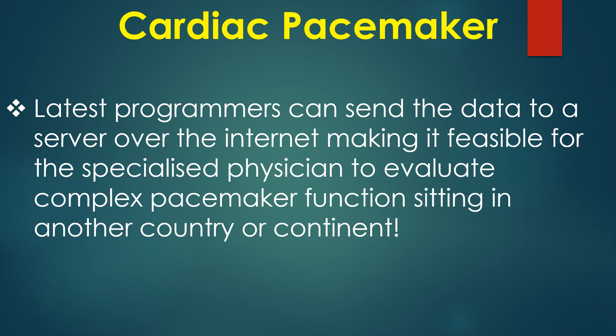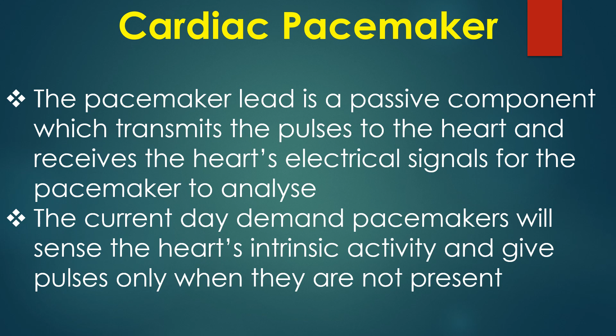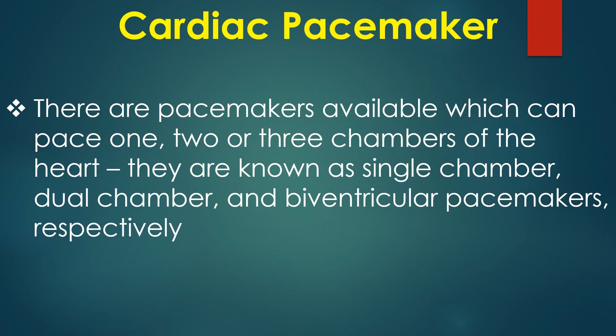The pacemaker lead is a passive component which transmits the pulses to the heart and receives the heart signals for the pacemaker to analyze. The current day demand pacemakers will sense the heart's intrinsic activity and give pulses only when they are not present. There are pacemakers available which can pace 1, 2 or 3 chambers of the heart. They are known as single chamber, dual chamber and biventricular pacemakers respectively.